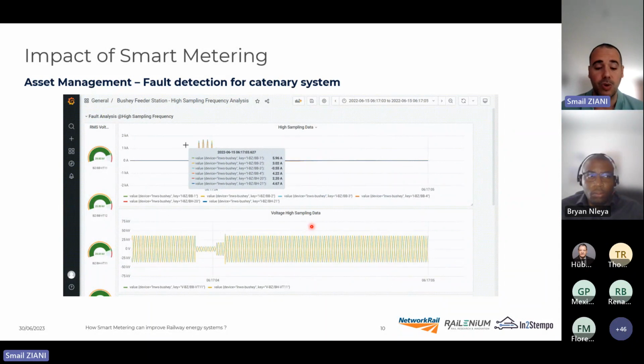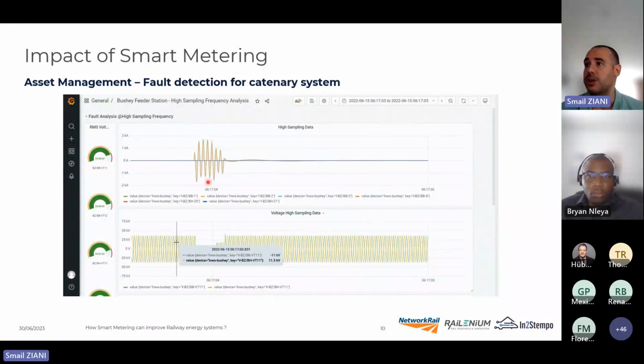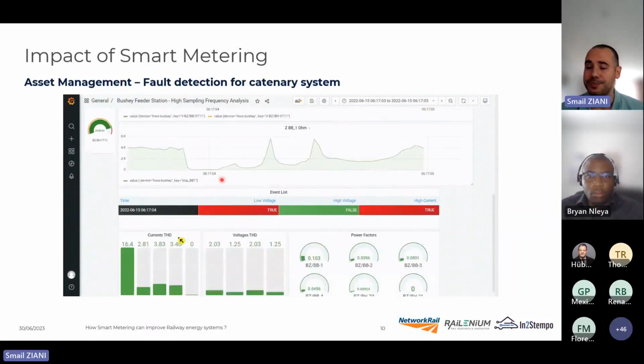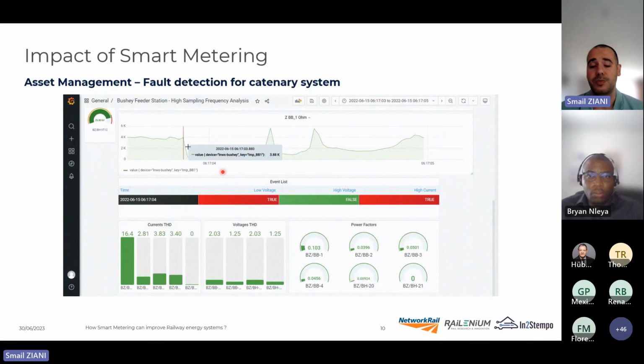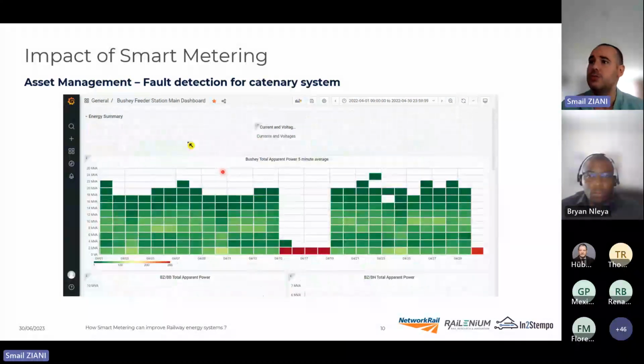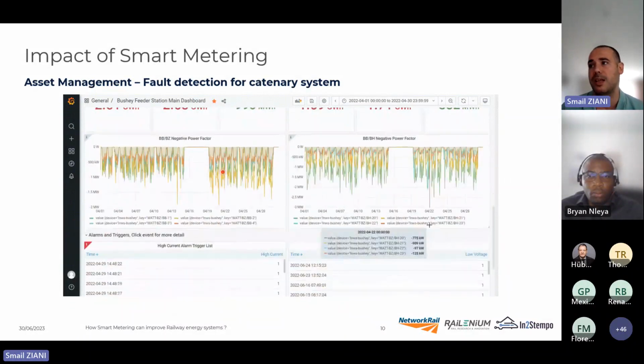And when it's necessary to have a high sampling frequency to get the raw data, like here, for example, we have the current and the voltage, we will use some triggers. So if you have a high value of current and a low value of voltage, we will start to make the acquisition. I will give you an example: 10 seconds before the event, during the event, and 10 seconds after the event, just to have this raw data to make some analysis.